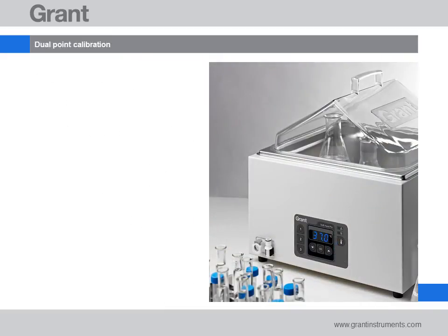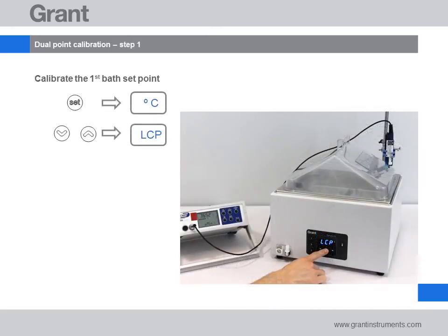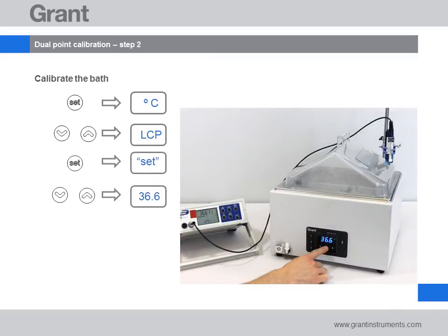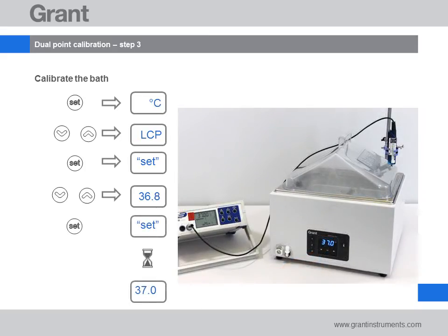Moving on to the dual point calibration. This consists of 2 points, a low and a high calibration point. To do this, press the Set button and, using the up and down keys, navigate to the screen displaying LCP. Press Set and then enter the reference thermometer value using the up and down keys. Press Set to enter the value and wait for the bath to automatically adjust to the set temperature. This now completes the low part of the dual point calibration.